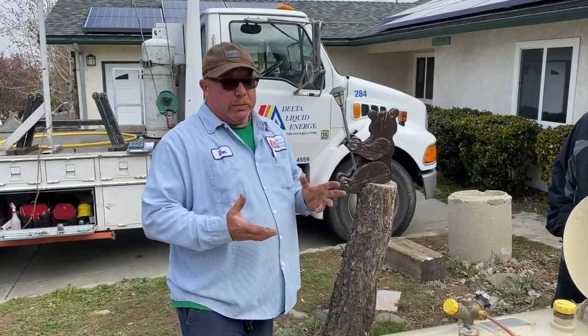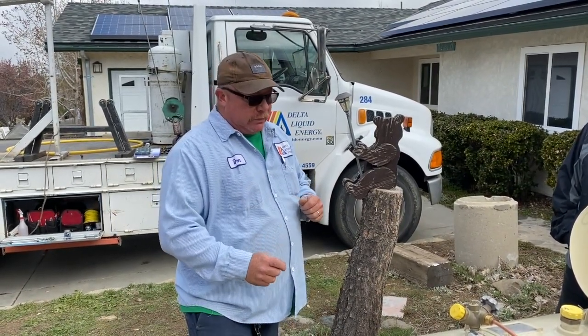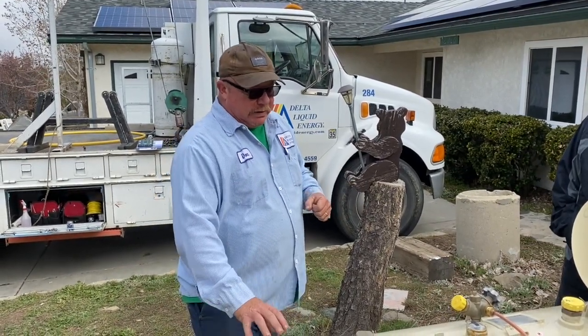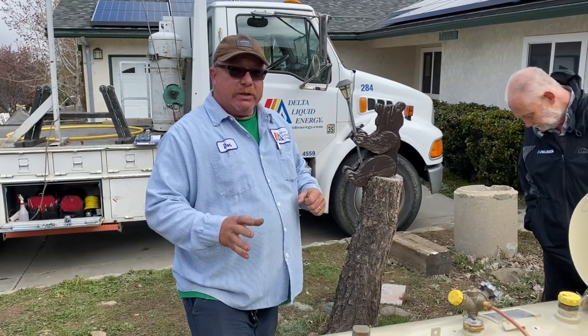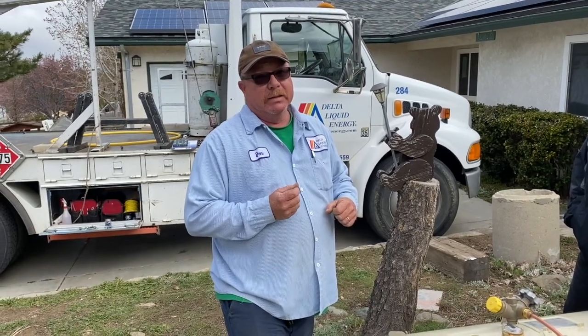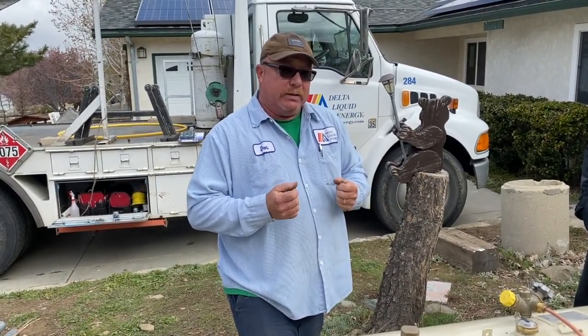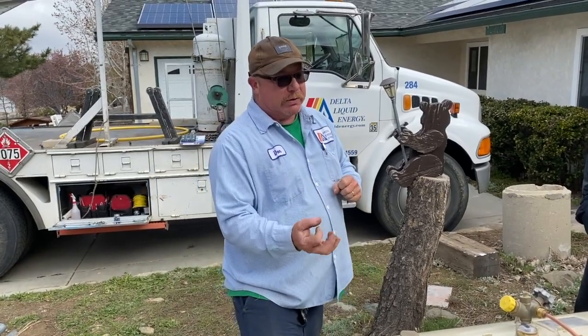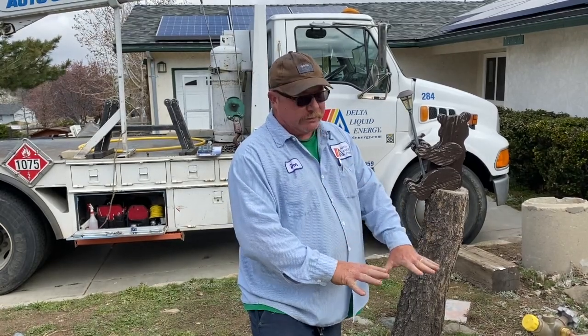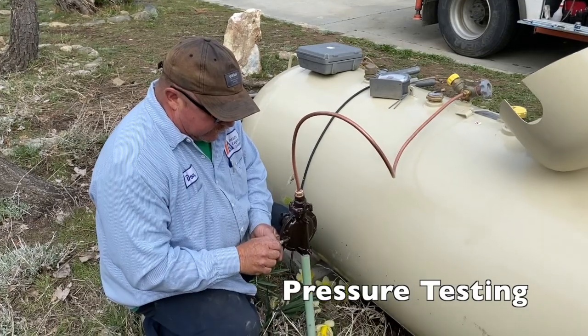The liquid propane boils at 44 degrees below zero. So when you put it in a capsule, it boils off until it reaches about 150 pounds of pressure and it brings the temperature of the liquid up to 60 degrees above Fahrenheit. That's what pushes into your house — it's the vapor, that's what burns. So the liquid just boils off. You use some pressure off the tank, it boils off a little bit more until it reaches a pound of pressure, which equals about 28 inches of water column.